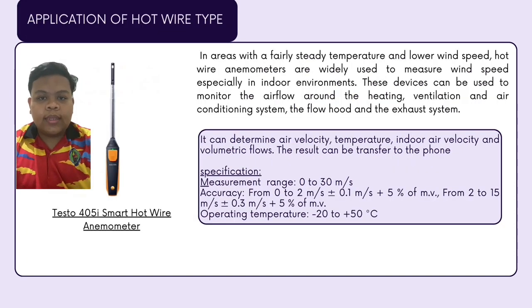Application of hot wire type is usually in industry for ventilating systems, where this device is usually used to measure wind speed, especially in indoor environments. This device can be used to monitor the airflow around the heating, ventilation, and air conditioning system, and the flow hood and the exhaust system.